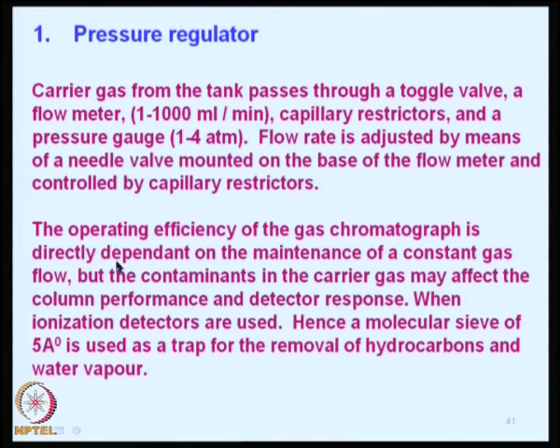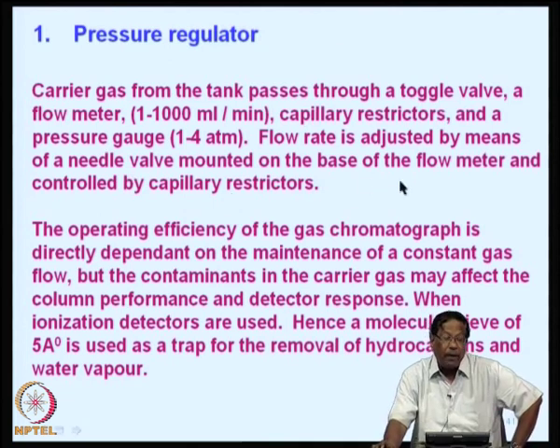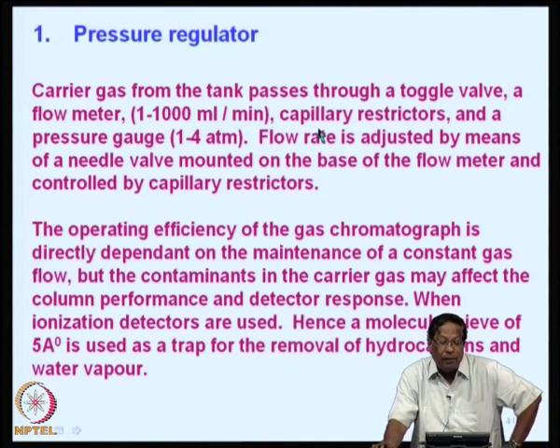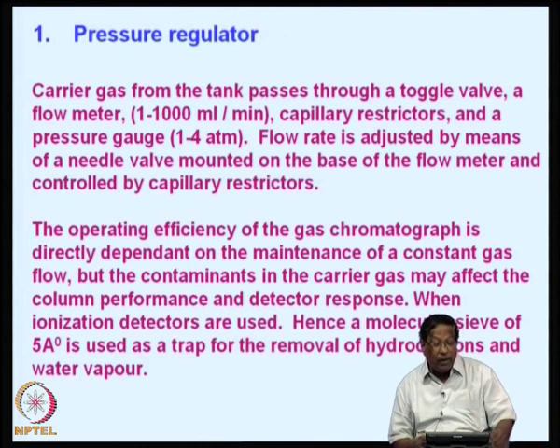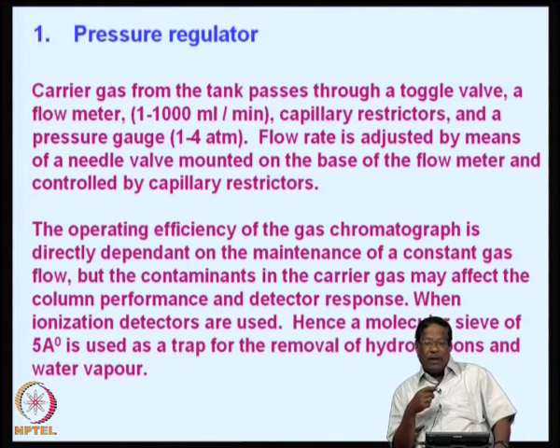The carrier gas from the tank passes through a toggle valve and a flow meter providing about 1 to 1000 milliliters per minute, with capillary restrictors and a pressure gauge of about 1 to 4 atmospheres. Flow rate is adjusted by a needle valve mounted on the base of the flow meter and controlled by the capillary restrictor. The operating efficiency of the gas chromatograph is directly dependent on maintenance of constant gas pressure, which controls the success of a chromatographic separation.